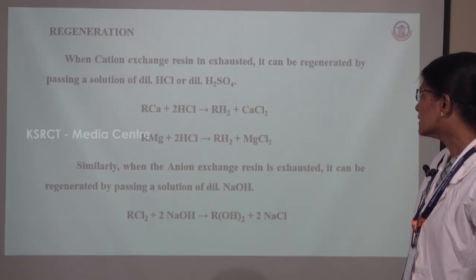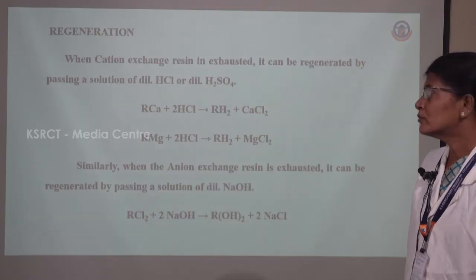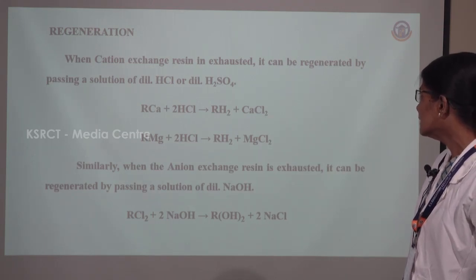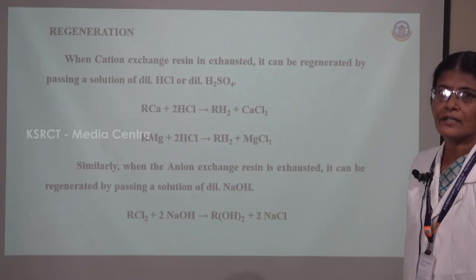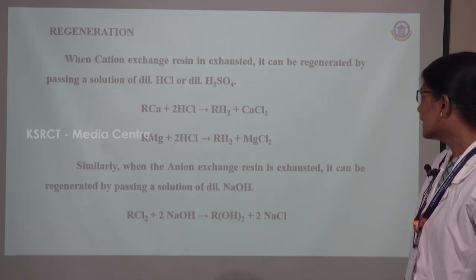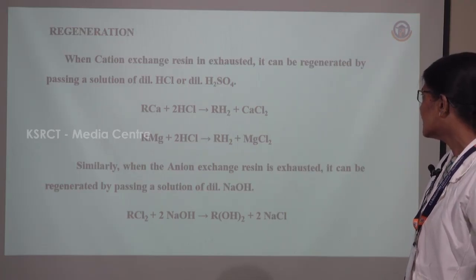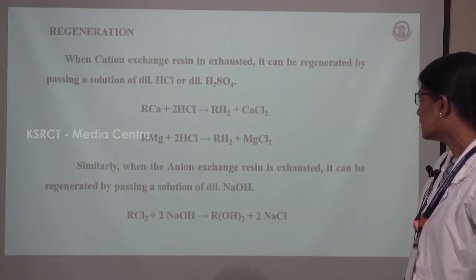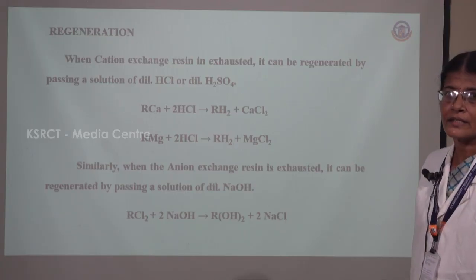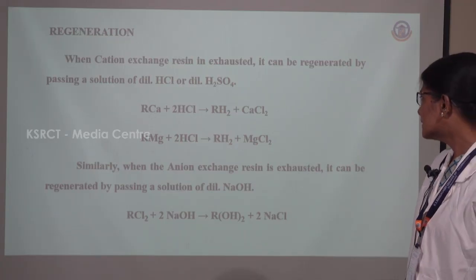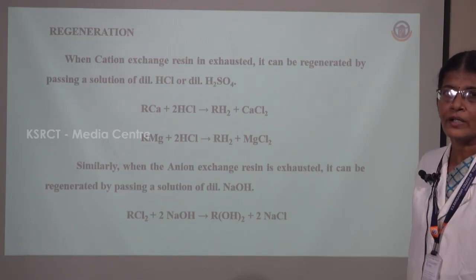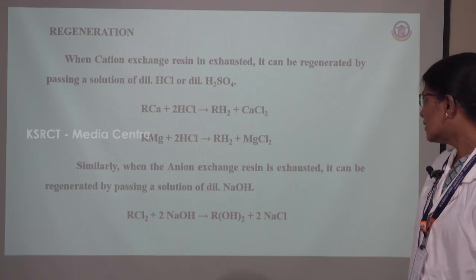After a particular stage, the bed will be exhausted and regeneration must be performed. The cation exchange resin can be regenerated by passing dilute HCl or dilute H₂SO₄. The reactions are: RCa + 2HCl → RH₂ + CaCl₂; RMg + 2HCl → RH₂ + MgCl₂. Similarly, if the anion exchange resin is exhausted, it can be regenerated by passing dilute NaOH solution: RCl₂ + 2NaOH → ROH₂ + 2NaCl.